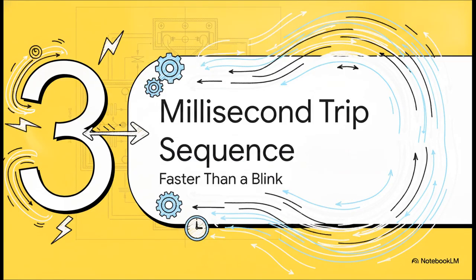Moving on to part three, the millisecond trip sequence, where we see things reacting faster than the blink of an eye. During a real high-pressure fault scenario, that internal arcing pressure shoots up almost vertically. We're talking about hitting 200 kilopascals in just 20 to 50 milliseconds. It completely proves why traditional electrical numerical relays, which actually need time to process signals and run calculations, are just way too slow to stop the explosion.